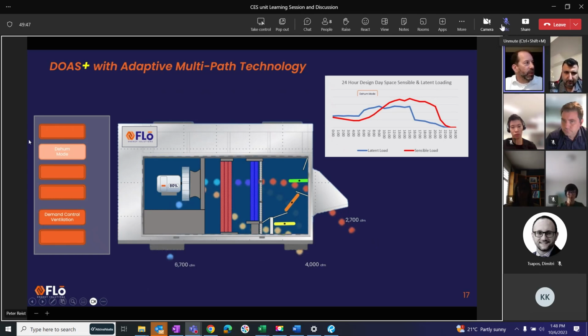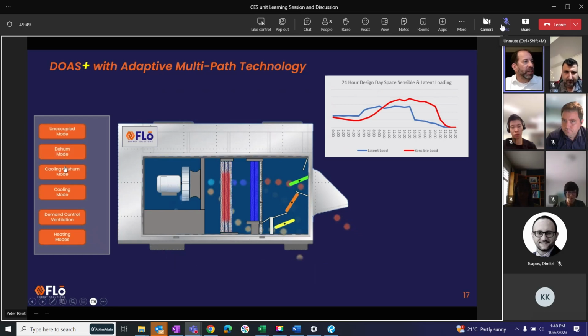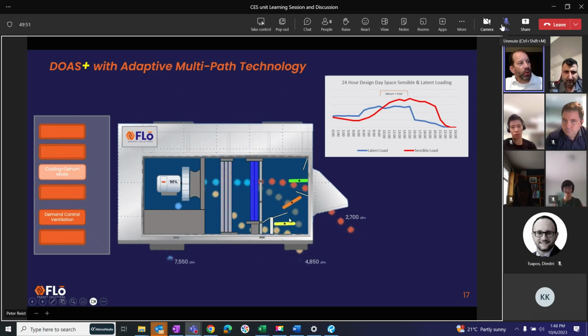As we go further in the day and we see that, okay, we don't need quite as much dehumidification, we need more cooling, this is where we go into a mixed mode where we let a little bit more of this return air come up over the coil. And so we get more cooling capacity, slightly less dehumidification capacity. Again, it all depends how much air we let come up here. Now we're running our fan speed at 90% just because of our static loads and static pressures, but we're maintaining a constant outdoor air volume.